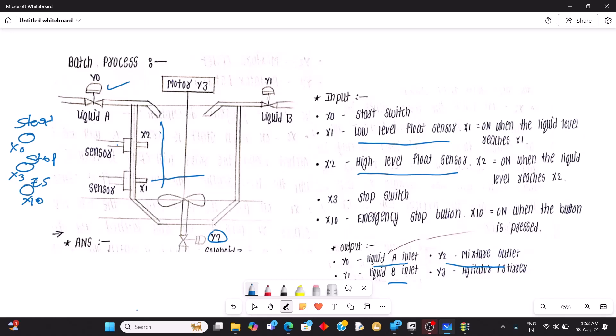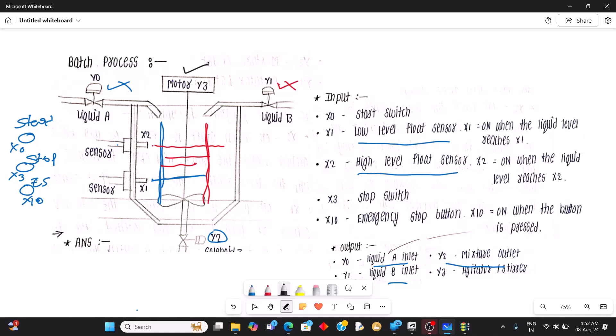When you start filling, it immediately starts filling the tank and reaches to X1, so Y0 will be stopped. Then Y1 will be triggered — the second liquid starts filling. When it reaches X2 the high level, Y1 will be turned off immediately and the motor Y3 will be turned on. It remains on for 30 seconds — but in the program we will take five seconds.